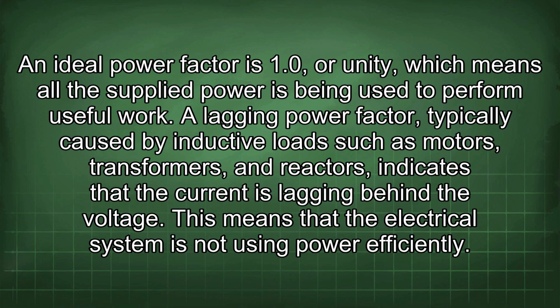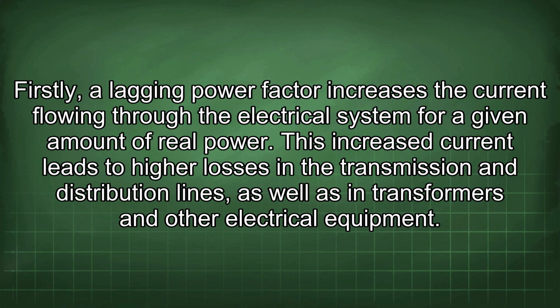work. A lagging power factor, typically caused by inductive loads such as motors, transformers, and reactors, indicates that the current is lagging behind the voltage. This means that the electrical system is not using power efficiently. Firstly, a lagging power factor increases the current flowing through the electrical system for a given amount of real power.